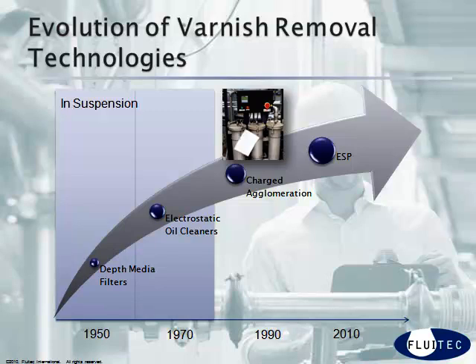Charged agglomeration was developed in the 1990s. It splits the oil into two streams, charging one stream with a positive charge and the other stream with a negative charge. When these streams are combined, the particles can agglomerate, grow in size, and can then be removed through the system's mechanical filtration. However, they do not have the ability to remove contaminants while they are in solution.